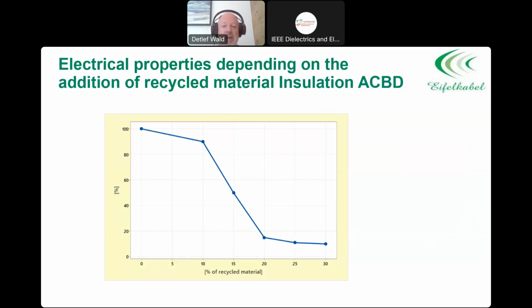Here is a short summary or sneaky peek, and I'm just looking now and I'm perfectly in time because there's a short sneaky peek about the electrical properties depending on the addition of recycled materials of AC insulation and AC breakdown. So the addition was here, and there will be more, like I said, in that secret paper that will be presented beginning of November. So what was done here was of new, not used polypropylene cables. A certain percentage of recycled material has been added to afterwards virgin polypropylene material, and a new cable was produced.